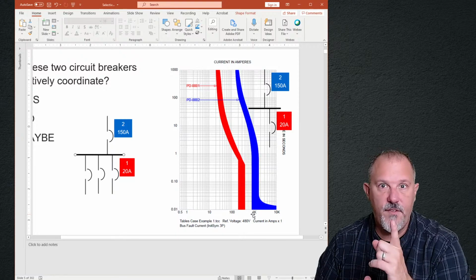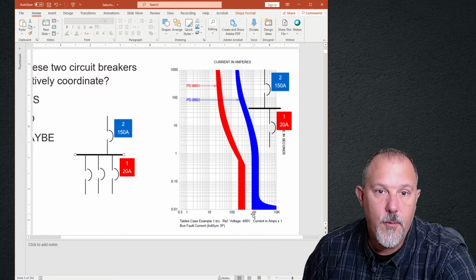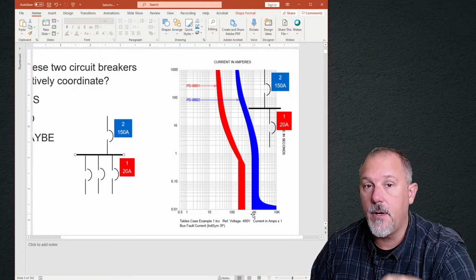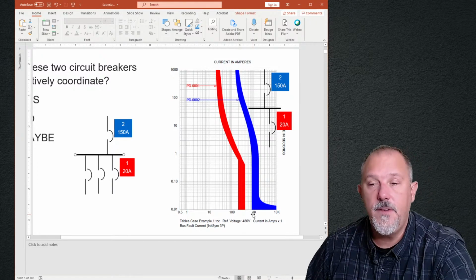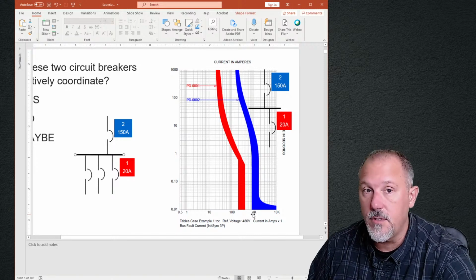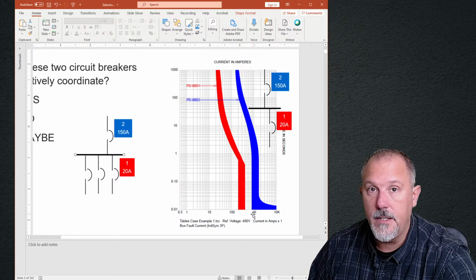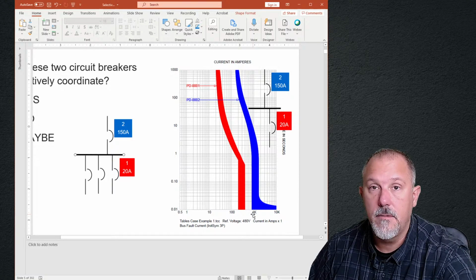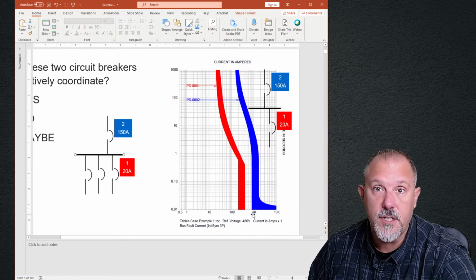Now, if you told them you have to do an evaluation of these two breakers based upon some level of fault current, even if you said, I'm not going to do the three-phase bolted fault current, okay, that's fine. You can pick something less. What is it? And what's your justification?